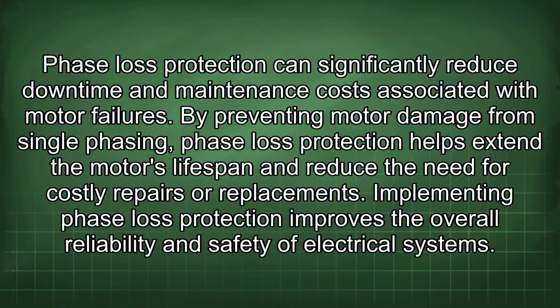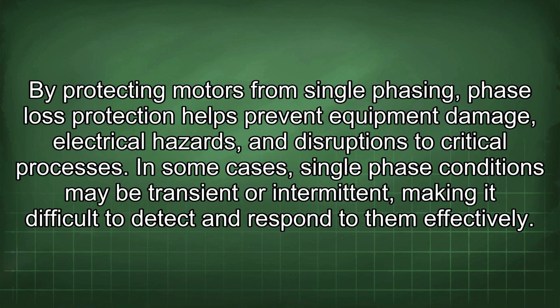Phase loss protection can significantly reduce downtime and maintenance costs associated with motor failures. By preventing motor damage from single phasing, phase loss protection helps extend the motor's lifespan and reduce the need for costly repairs or replacements. Implementing phase loss protection improves the overall reliability and safety of electrical systems. By protecting motors from single phasing, phase loss protection helps prevent equipment damage, electrical hazards, and disruptions to critical processes.